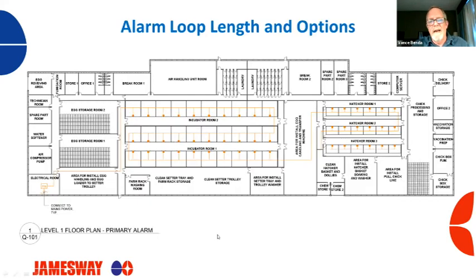Now, I have to have this slide up here because there's always options on where you mount the alarm box. But I basically want to show everybody how long these loops can be. So here we have our alarm control down here. If you follow the wire, it goes up through these incubators, across through these incubators, across through these incubators. Then we go over here to your hatcher, and it does the same thing. It just works its way through all these hatchers. And so that's when I say these alarm loops can get incredibly long. That's a long one there. We can make it work if this is how you choose, but we could also do different things.